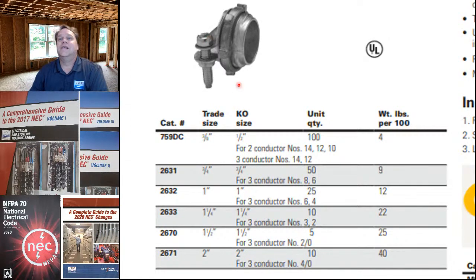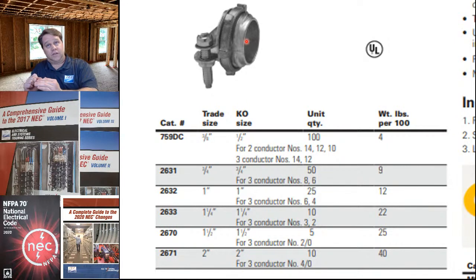So, how many cables can you stick through these fittings legally? Well, the code doesn't care. The code doesn't address it. That's all per the manufacturer. And now, because we do need listed fittings, we also need to follow the instructions. Once you have a listed product, you have to follow the instructions. That's what 110.3(B) says. So, how many can you put through there? Get with the manufacturer and they'll let you know.